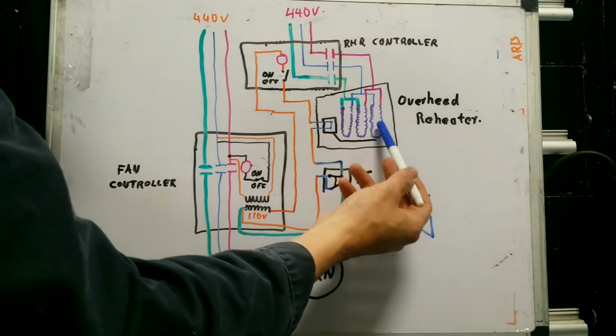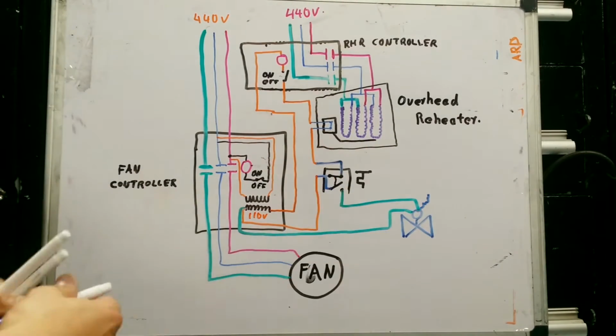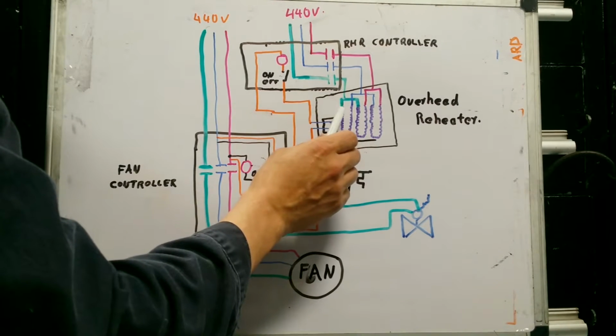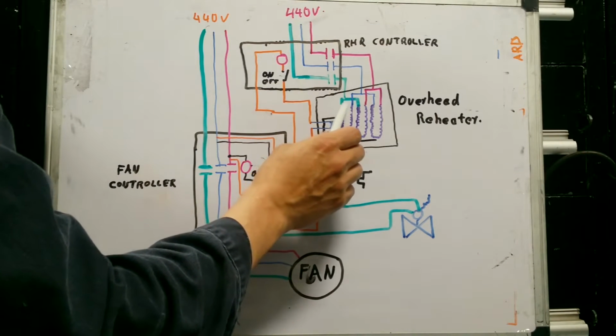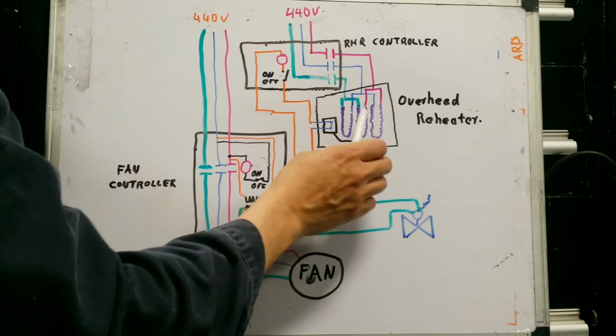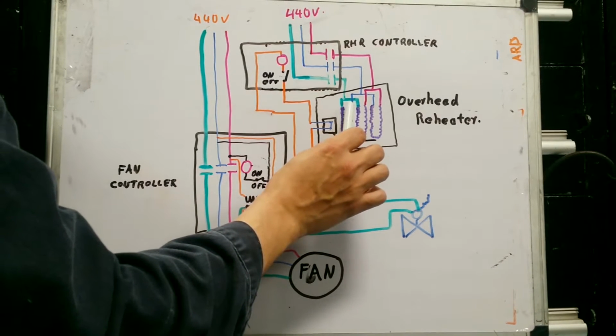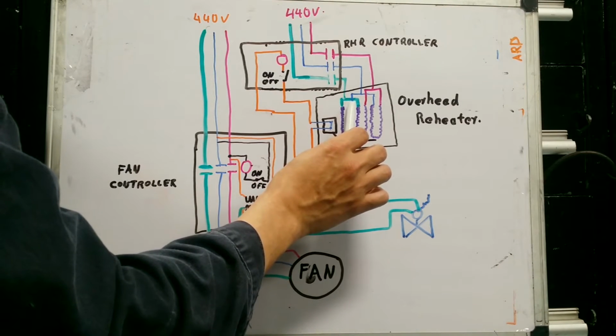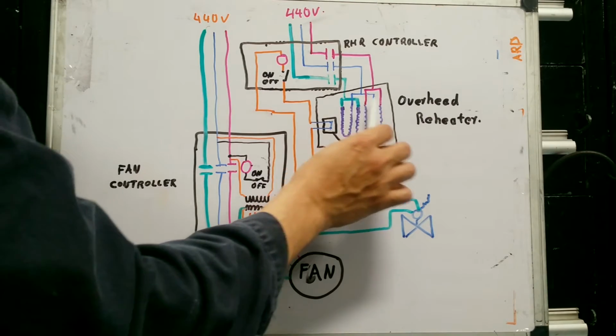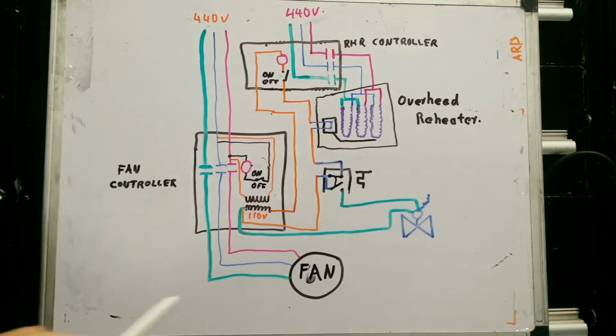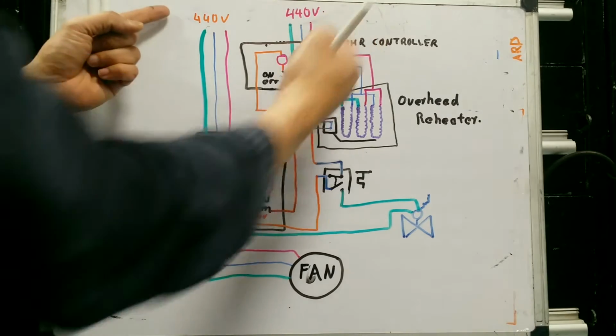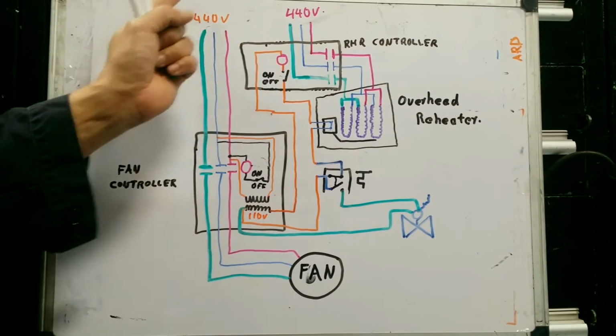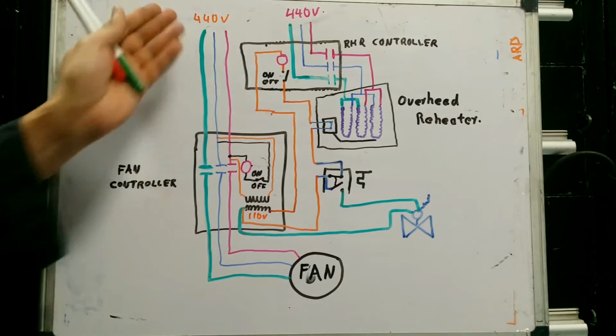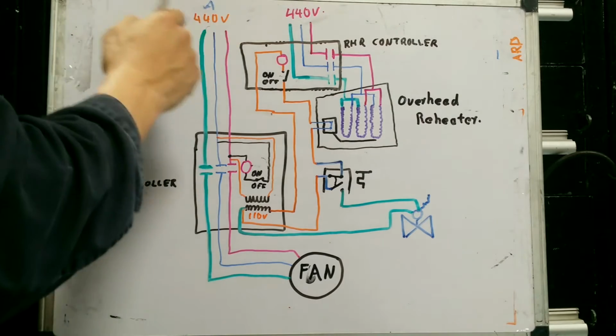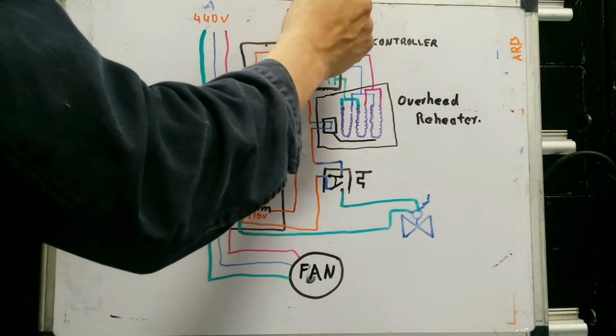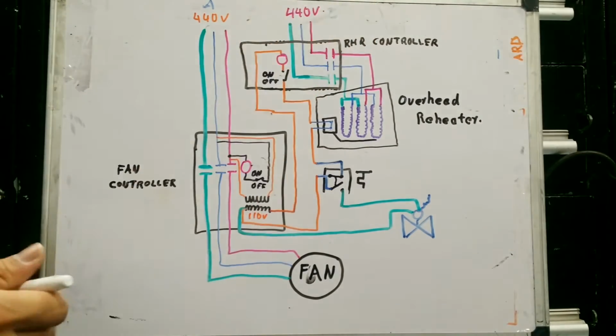As a matter of fact, these are the heaters. You see, they are connected in a way that the first one gets power from the green wire, the second one gets power from the blue, and the third one from the remaining phase, and so on and so forth, so they are balanced. Now, there are two different power sources, two different breakers per se. This breaker, let's say breaker alpha, gives power to the fan. This is breaker bravo, which gives power to our heater.